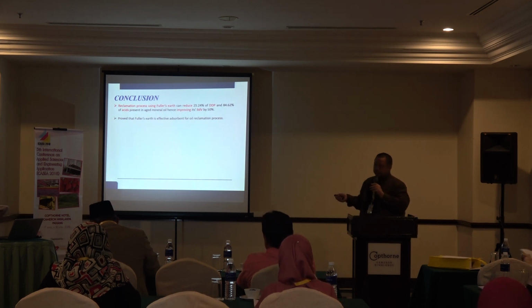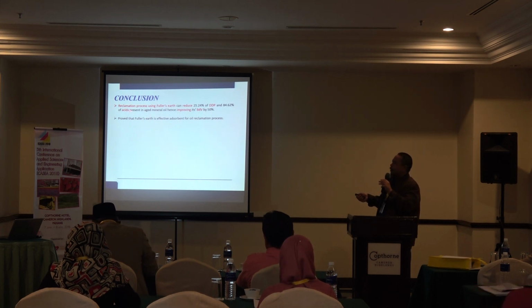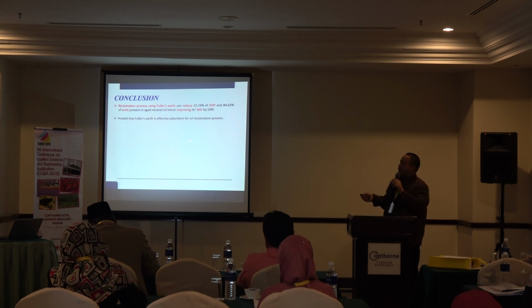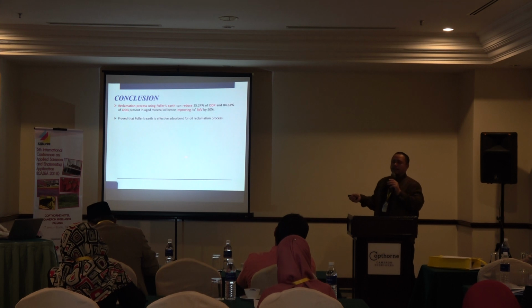So for the conclusion, I can say that it is proven that by using reclamation with fuller earth, there is a reduction of acidity in the oil and also an increase of the breakdown voltage or dielectric strength of the transformer oil itself. So it proved that fuller earth is also an effective adsorbent that is mainly used by other researchers.